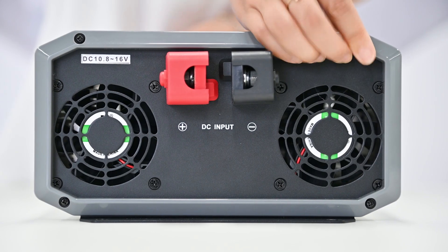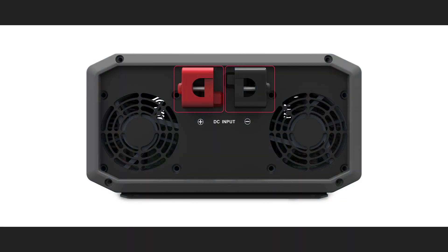On the other side, we have the positive and negative terminals of the battery bank. iPower Plus series supports lithium batteries, and these are the cooling fans, which help to ventilate the inverter. It is worth mentioning that in an off-grid system, it's best to connect the inverter directly to the batteries, rather than connecting to the charge controller's load terminals. For cabling and installation, please refer to the manual.